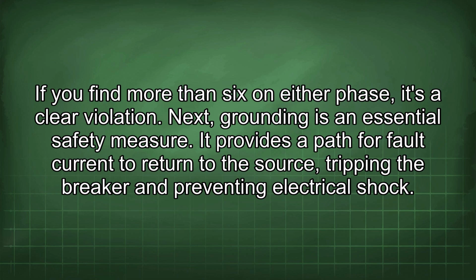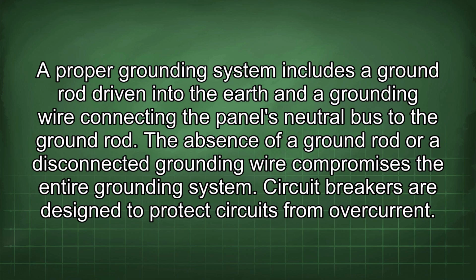Next, grounding is an essential safety measure. It provides a path for fault current to return to the source, tripping the breaker and preventing electrical shock. A proper grounding system includes a ground rod driven into the earth and a grounding wire connecting the panel's neutral bus to the ground rod. The absence of a ground rod or a disconnected grounding wire compromises the entire grounding system.